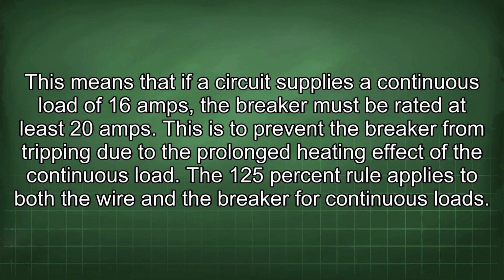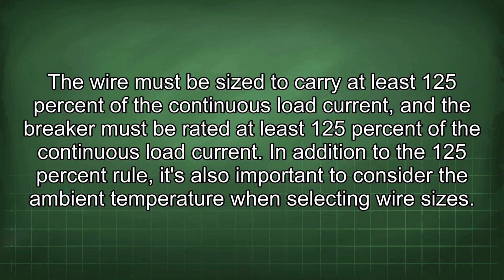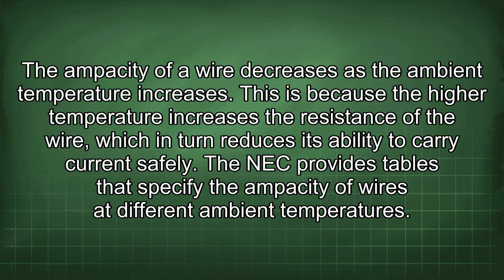The 125% rule applies to both the wire and the breaker for continuous loads. The wire must be sized to carry at least 125% of the continuous load current, and the breaker must be rated at least 125% of the continuous load current. In addition to the 125% rule, it's also important to consider the ambient temperature when selecting wire sizes. The ampacity of a wire decreases as the ambient temperature increases.